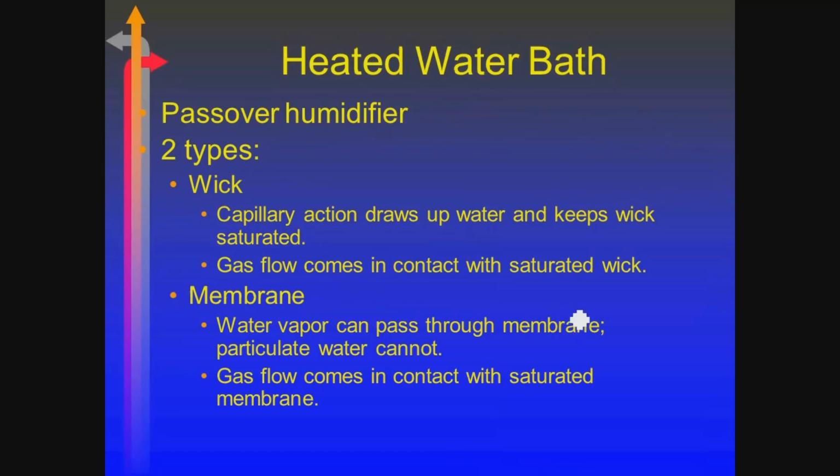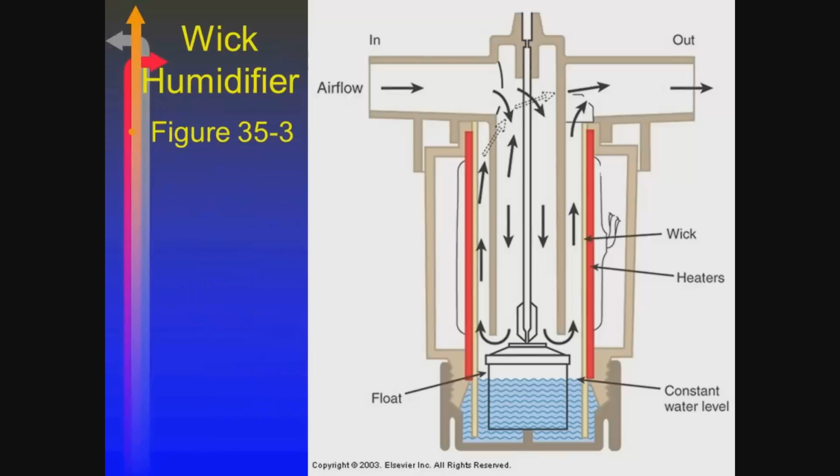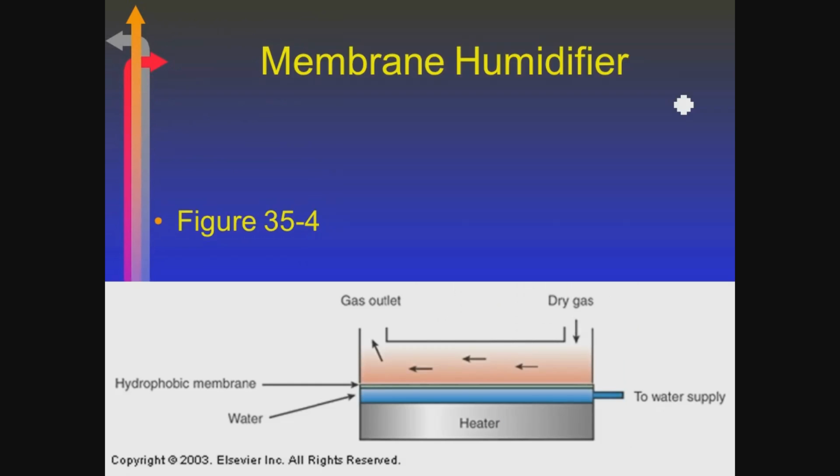And then finally, there's a heated water bath. I think Mary probably talked about the wick versus the membrane. Both are functional. The wick just draws up the humidity, so any gas passing by becomes humidified, whereas with the membrane, the dry gas comes in and goes over the surface of this. This membrane is hydrophobic, but the water vapor is allowed to pass through and is picked up, and you humidify the gas in that fashion.